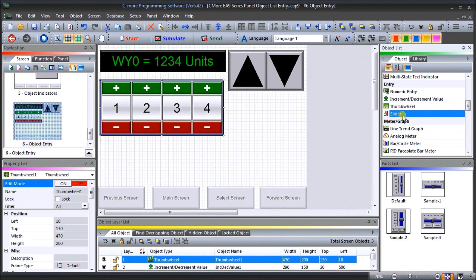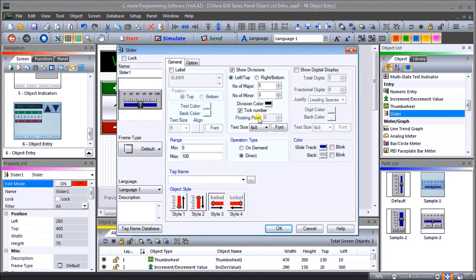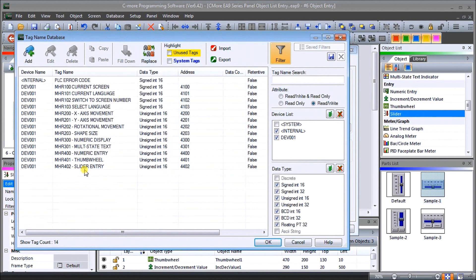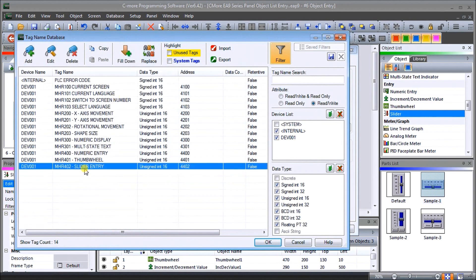Under slider — as I increase the slider on a control panel it will actually increase and decrease numbers in our PLC. We'll take sample number one and drag it onto our screen. We have a range of zero to 100; we'll leave it as zero to 100 representing zero to 100 percent. Our tag name will be MHR 402, which is Modbus address 4402. Hit OK.